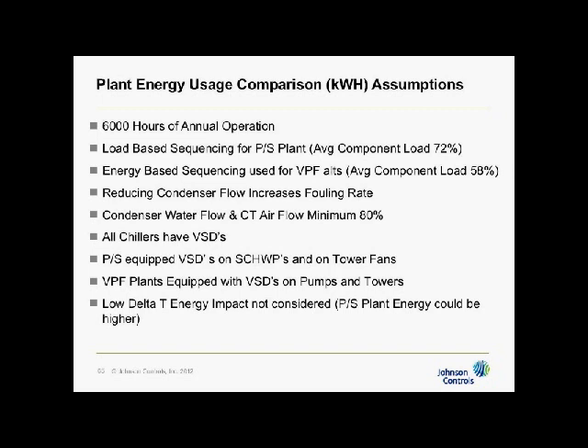As before, all the chillers have VSDs, variable speed drives. The primary-secondary system had variable speed drives on the secondary chill water pumps and also on the cooling tower fans. The VPF plants were equipped with variable speed drives on the pumps and cooling tower fans. We did not include any impact of low delta T. That is going to be left for another analysis. So here are the results of this work.